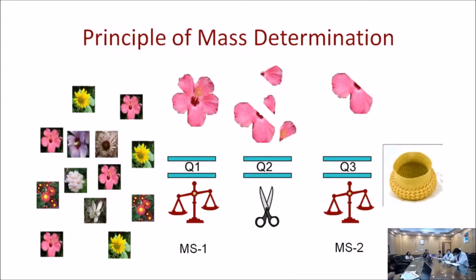In quadrupole 2, what it does is that it splices, it fragments them. When a molecule is getting fragmented, it gets converted into a lot of molecular species or fragmented ions. These fragmented ions are again weighed in quadrupole 3. The quadrupole typically behaves like a weighing balance, and quadrupole 1 is behaving as a weighing balance too, but quadrupole 2 does the fragmentation process.